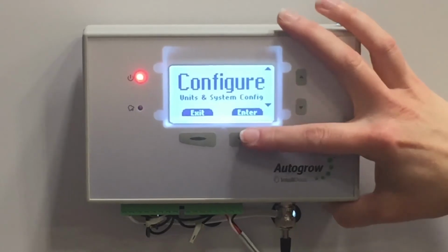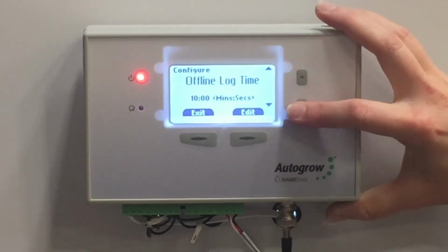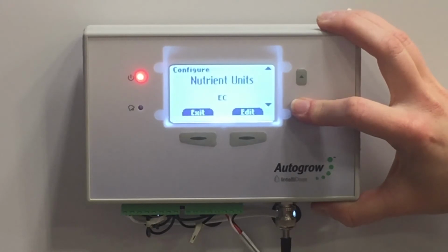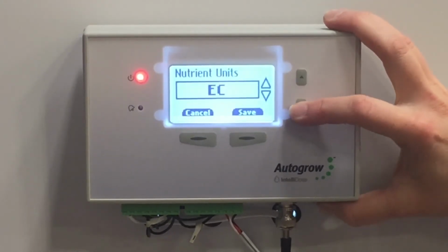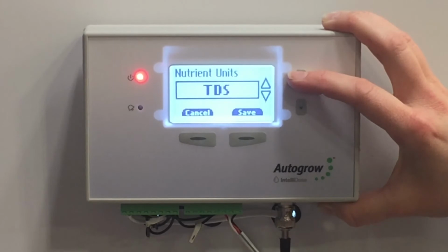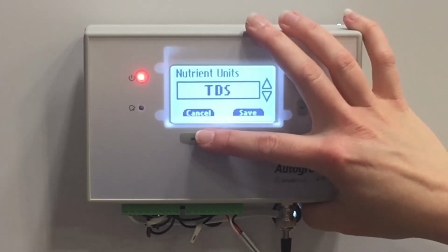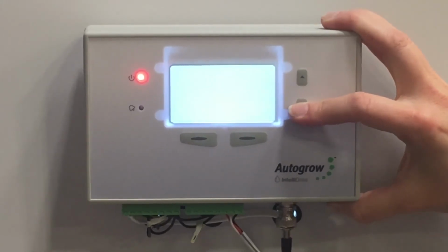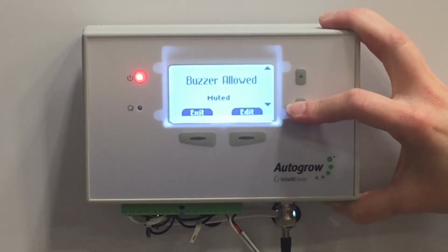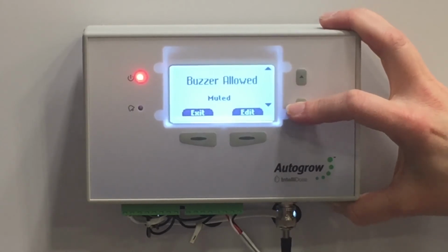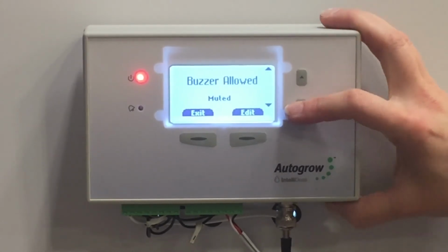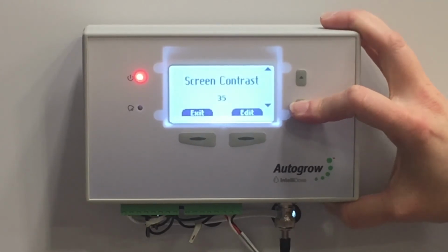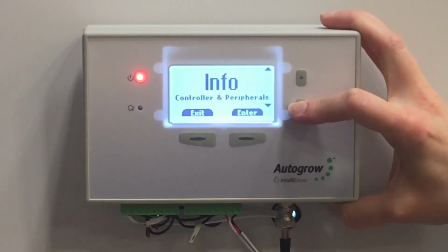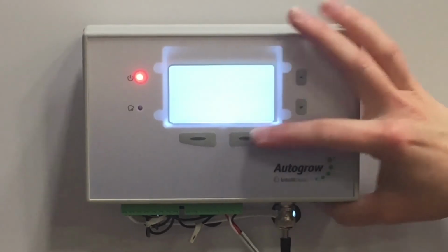We have our clock settings, and then we have basic configuration settings where we can log in our log times, nutrient units. We have the ability to do EC, CF, and TDS, so you can change the units to whatever you're comfortable with. Date format, temperature units. If you want to have the alarm buzzer muted on the unit itself so that the controller itself doesn't make any noise, you can mute it here. We have screen contrast, backlight, and then we can go into the info, which tells us a little bit about the controller, all the versions.